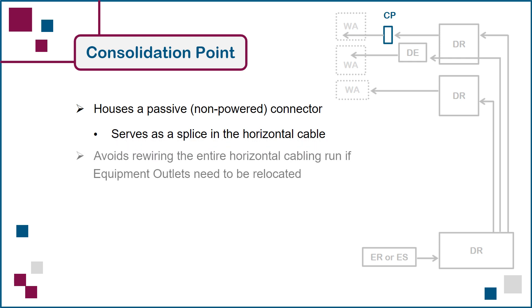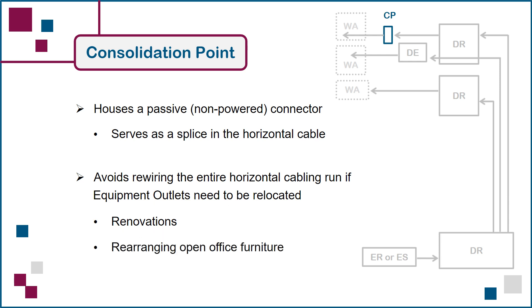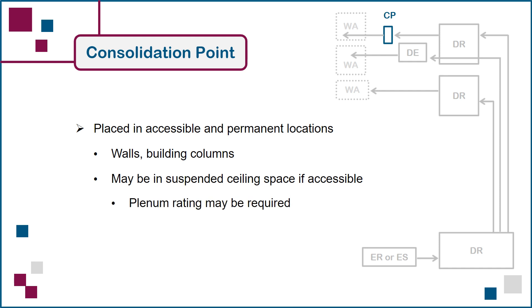Examples include relocating an individual equipment outlet in an office that is being renovated and the rearrangement of multiple open office work area partitions. Note that a consolidation point can also be retrofitted into an existing installation, which can save money by lowering the total length of cable and amount of labour required for the planned work area changes. Like the distributor enclosure, the consolidation point can be placed in a variety of locations on the floor. Note that ceiling installations may require the use of products with a plenum rating if the proposed location is classified as an air handling space by the authority having jurisdiction, or AHJ.